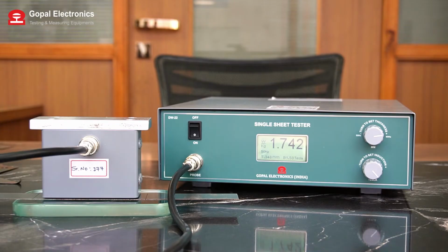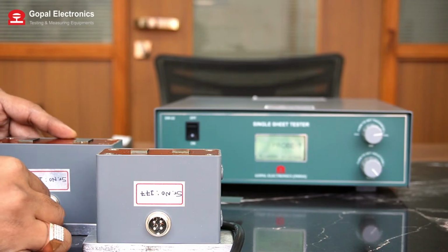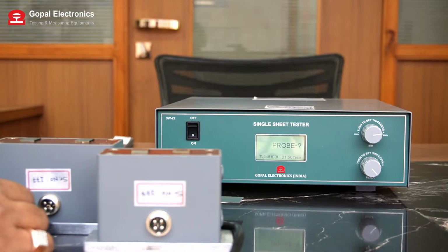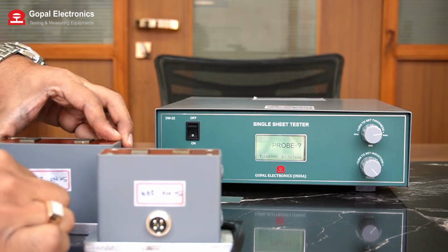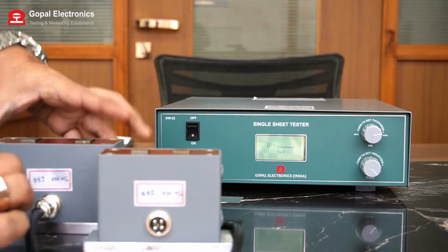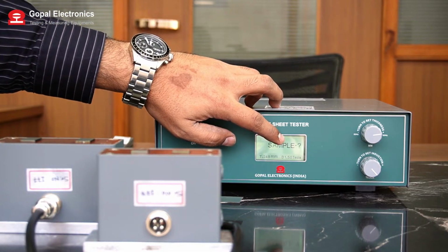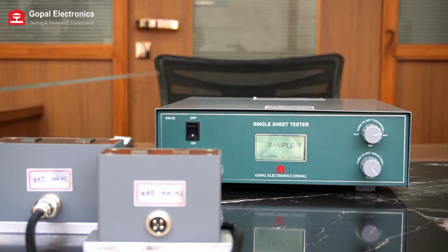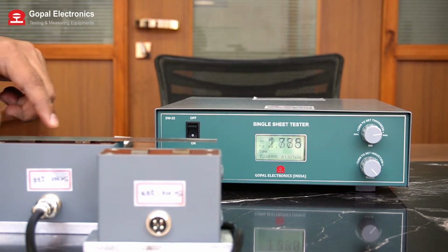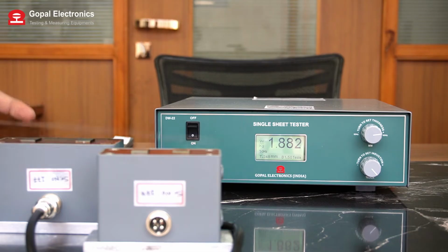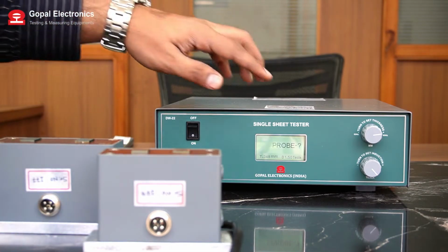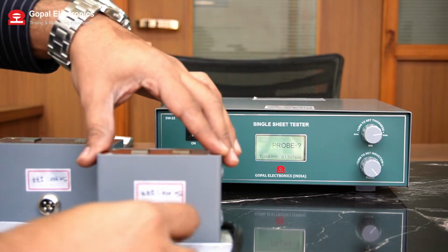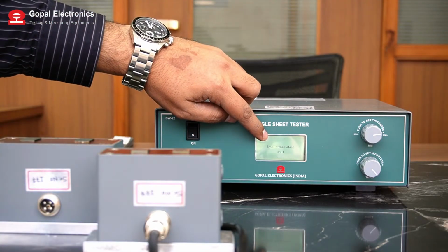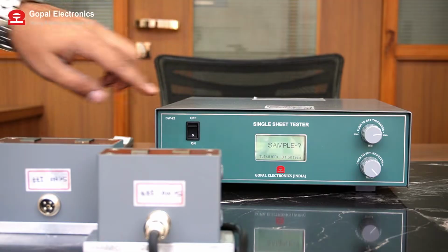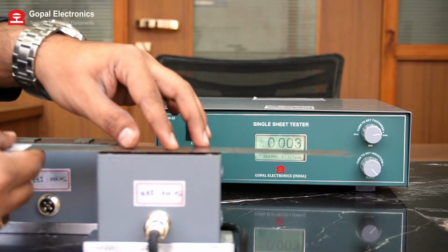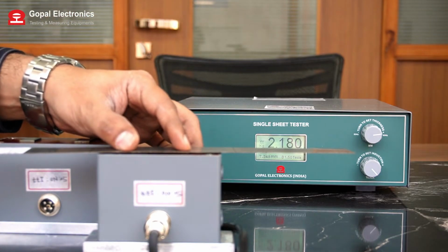This equipment can detect the probe as well. Right now I am connecting a big probe, you can check in the display. Right now over here you can see probe and question mark. I am connecting a big probe. You can see big probe connected, asking for the sample. If I put the sample on the probe, it will show the reading. Okay, now I am removing the probe. You can see it is asking for the probe. Now I am connecting a small probe. You can see small probe detected. Now asking for the sample. The same sample I am placing on the probe. You can see the reading is coming.